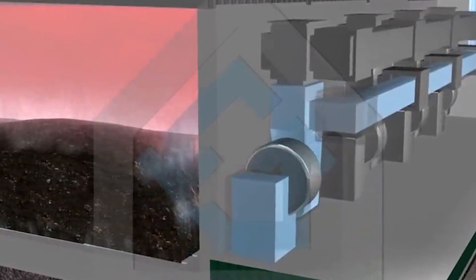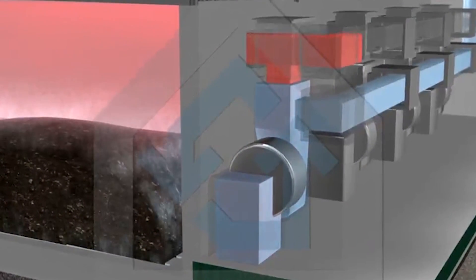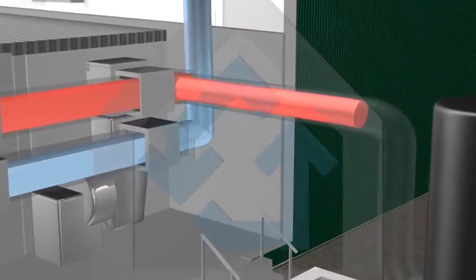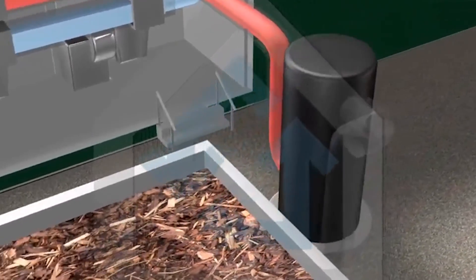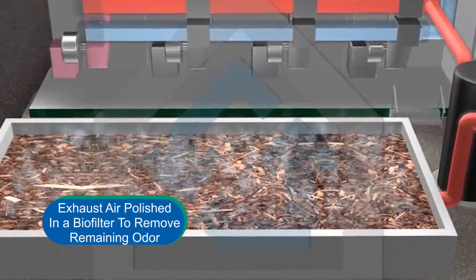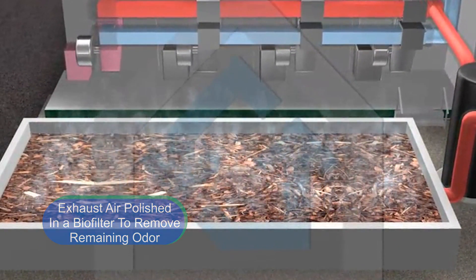Exhaust air from the IVC tunnels will be mixed with exhaust air from the aeration bay and SmartFerm digesters, and treated in an acid scrubber, which will remove 95 percent of the ammonia contained in the air stream. Following pre-treatment in the scrubber, exhaust air will be polished in a biofilter to destroy remaining odor-causing compounds.